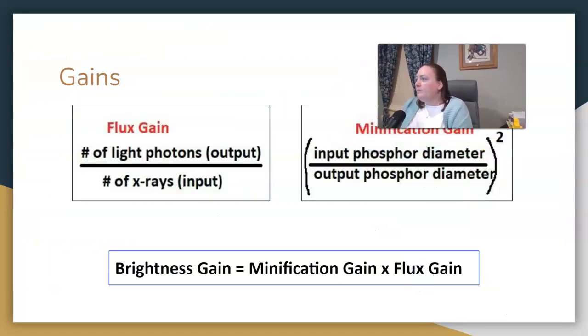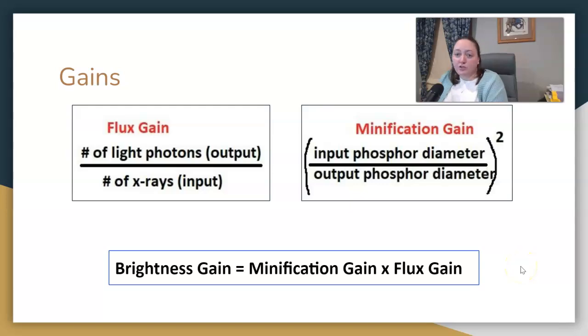There are some formulas involved. I think we should know these formulas. But do I think that we are going to need to do this math? I do not. And maybe we will in coming years here. But I think we should know what flux gain compares. And so this will be light photons to starting x-ray photons. Minification gain is about the diameter of input and diameter of output. Brightness gain will be these two things multiplied together.